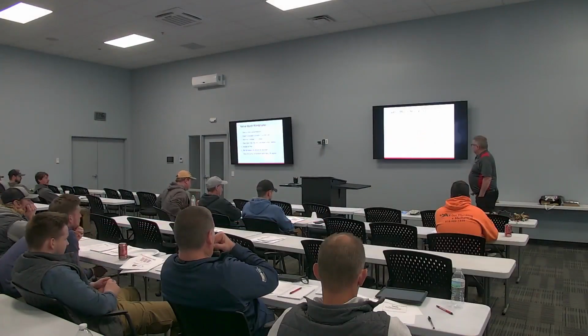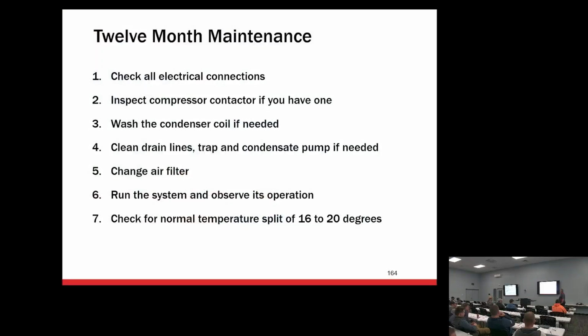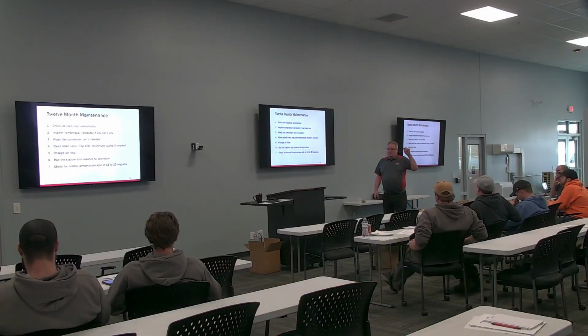Okay. So as far as maintenance, checking all connections, inspecting the contactor to make sure it's clean. Obviously wash the condenser, change the air filters, clean the traps, the condensate from the furnace as well as from the coils, change filters, check for normal temperature split. So this is in the heating. This is something we can simply do on a normal startup to check for my temp rise. Okay. A couple other things.